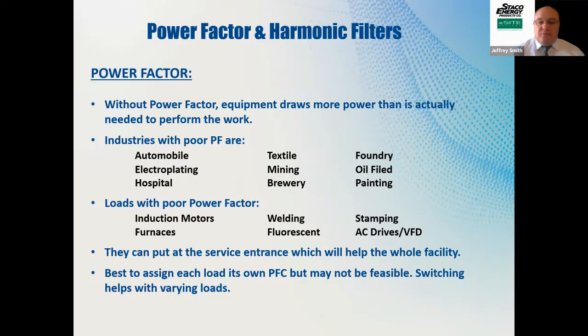Power factor correction, that's what it really is. When you have a lot of motors, drives, that type of thing, it can affect your power factor, meaning you can have a very low power factor. Some parts of the country, they charge penalties. The utilities will charge a penalty if your power factor is less than 0.95. Some areas, they don't worry about that. However, in certain areas of the country, the power companies don't have enough power going out, so they're going to their large customers that use a lot of power, requesting that they put in power factor correction so they can use the full amount of power that they have and not buy power that basically is not used at all.